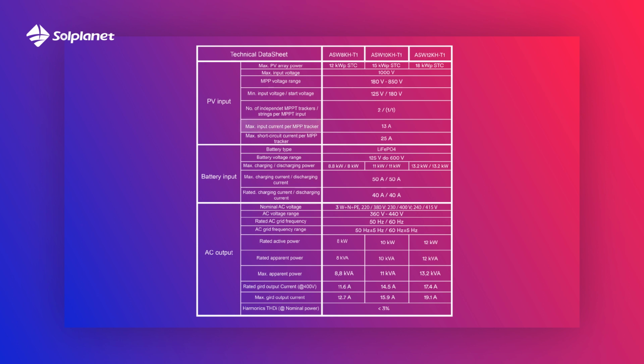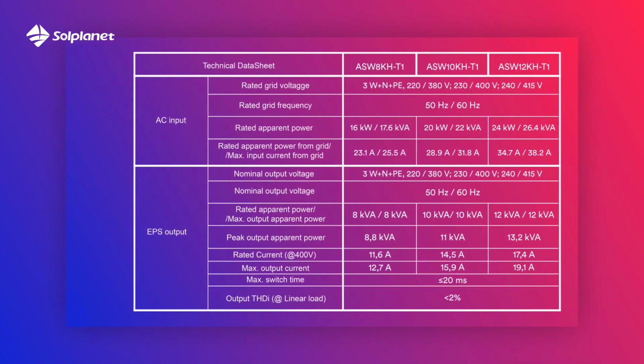Max input current per MPPT is 13 amperes. Max short circuit current per MPPT is 25 amperes. Max input voltage is 1000 volts. MPP voltage range is 180 volts to 850 volts. Minimum input voltage is 125 volts. Minimum start voltage is 180 volts. We have two MPP trackers, one string on one MPPT. Max EPS output power is the same as hybrid inverter power. For 8 is 8, for 10 is 10, for 12 is 12 kilowatts.